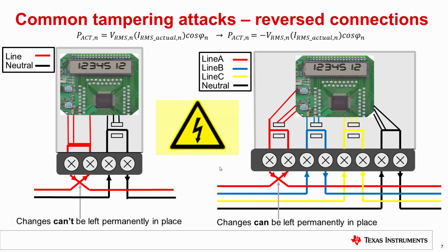For a three-phase system, one possible reverse connection configuration is to only swap the line in and line out wires for one phase. For a balanced load on each phase, this would cause a total energy consumption of 1/3 of the correct energy consumption, because the negative readings from the swapped phase would cancel out the positive readings of another phase. To help detect this form of tampering, the sign of the active power should be monitored, since it may indicate reverse connection tampering.